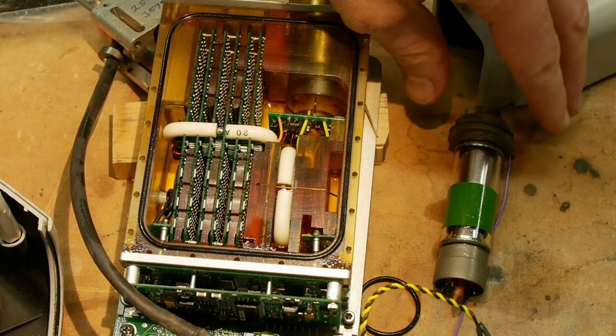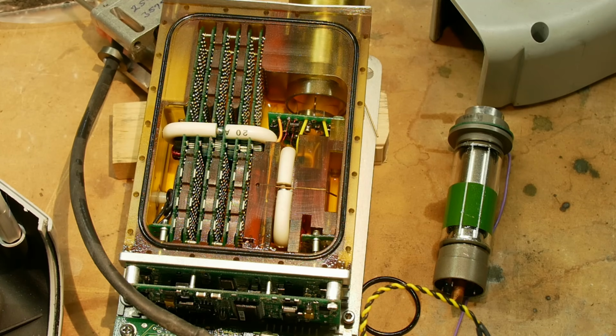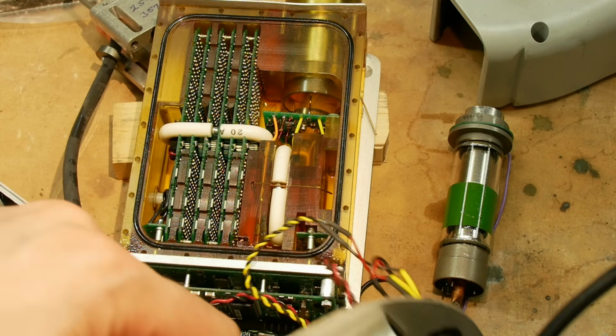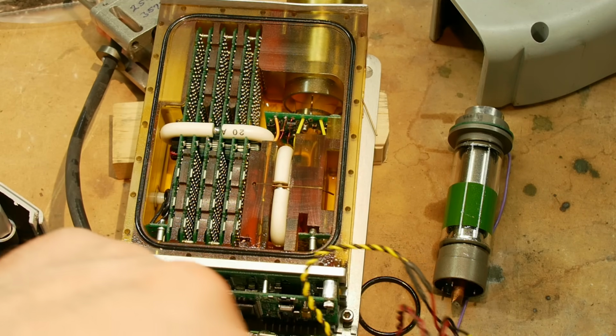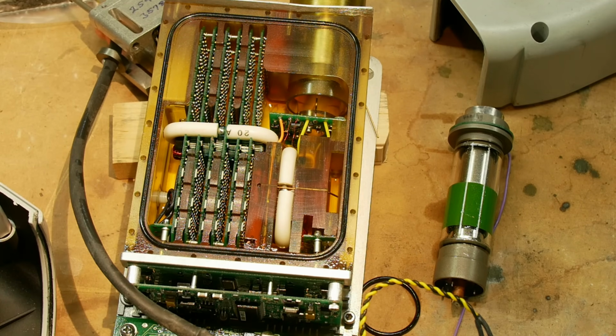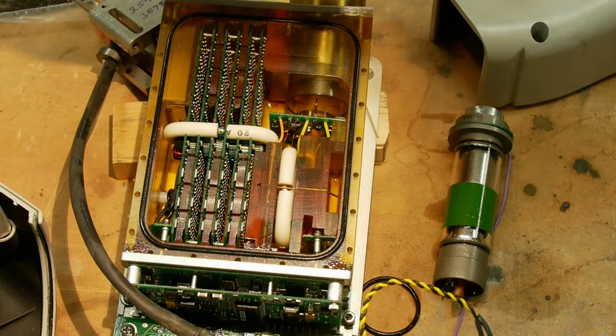I did actually find out what caused this whole thing to fail. It doesn't emit X-rays. You pull the trigger and the red light comes on, so the circuit thinks it's emitting X-rays, but hold it up to the Geiger counter, no X-rays come out. So that pretty much narrows it down to either a bad power supply or a bad tube.